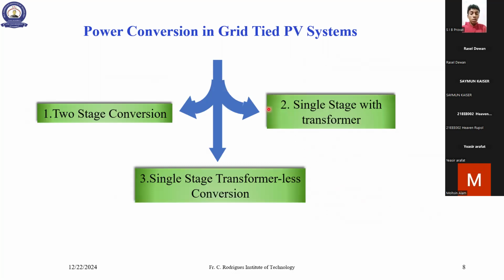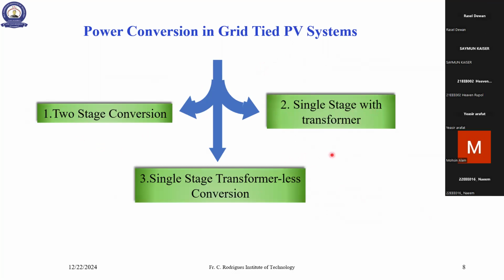Now, power conversion in grid-tied photovoltaic systems. There are three types of power conversion. One is two-stage conversion. Another is single stage with transformer, and the third is single stage without transformer. I am talking about single phase systems. I am not talking about three-phase systems in my seminar. The two-stage system means there are two stages. These two are single stage systems, which means there is only one power conversion stage, one with a transformer and the other without a transformer. So one by one we'll see.